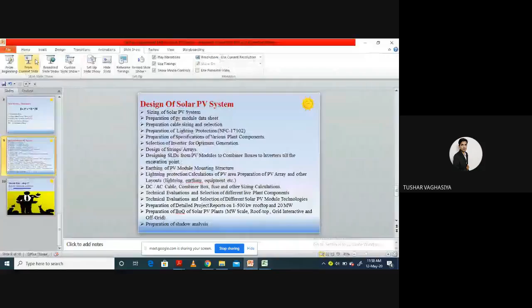Preparation of the PV module data sheet, as I already shared with all of you — data sheet of the PV module and selection of the PV module, cable sizing. There is DC cabling and AC cabling, how to select the cable for your solar power plant, and the requirement of lighting protection. We use a lighting arrestor for this lighting protection as per the standard NFC-17102.